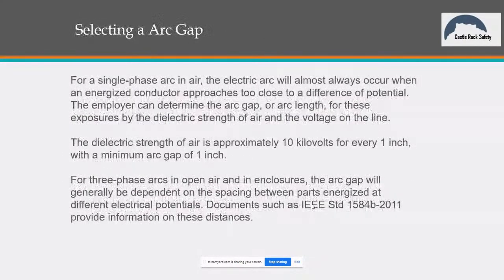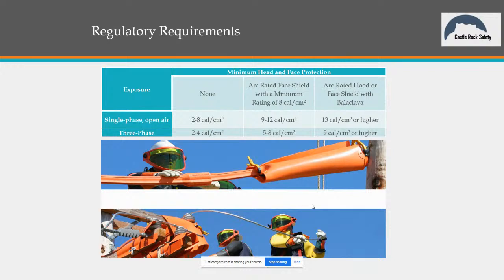What they determined also was that an arc flash in open air for a lineman is a little bit different than you standing in front of a panel board. When I'm up in a bucket, a lot of times I'm working with my hands up, the exposure is above me. And so when that arc occurs, it's going to dissipate in a 360-degree sphere, and the heat's going to travel up, and the distance from my face to that arc at a downward angle is longer than if I'm straight across from it.